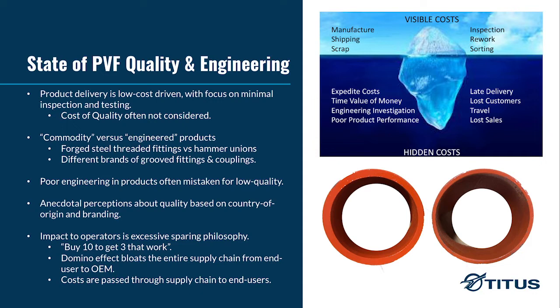The other example is in the grooved space. When you look at grooved fittings and couplings, you find there is a design code that offers about half of what's needed. When you look at different manufacturers and the same product, you see some differences. What you see in the bottom right of the slide are two fittings — same size (four inch), same style (45 elbow), same material, same pressure rating, made for the exact same application. Can anybody tell me what's different between the two?